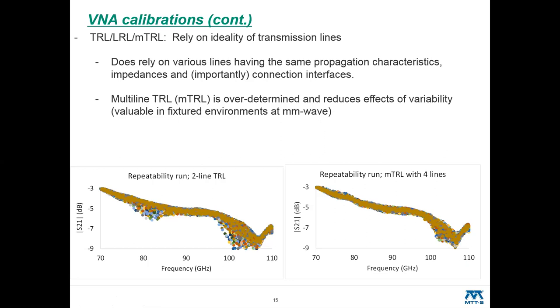That's particularly popular in the on-wafer metrology world. One example shown here in the lower left uses a basic two transmission line calibration. The calibration was done ten times and the same device was measured after each cal, and this is the scatter in that data. You can see a couple of areas of divergence, which in this case was due to the touchdown on one of the lines being problematic because of some pad damage. This is an on-wafer measurement.